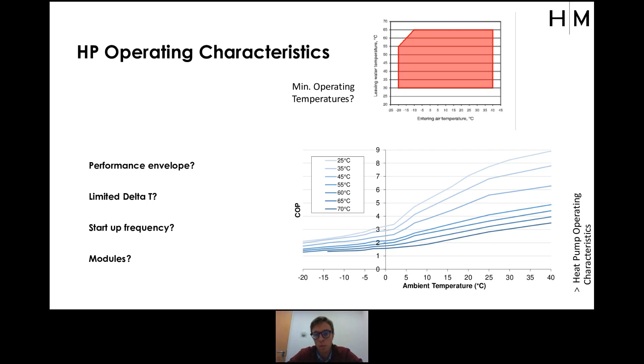And then just going on to modules, which a lot of that is to do with efficiency as well. So turn down part load efficiencies. You want to consider those at an early stage as well to impact on your plant area requirements, especially for external air source heat pumps. You can quickly increase your requirements significantly when looking at different types and having modules, because they have to sit quite far apart based on the cold pluming and defrost issues.